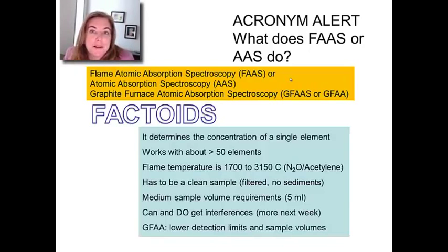Now some factoids about atomic absorption. First, it really is a technique that measures a single element. It's not an atomic spectroscopy that simultaneously looks at everything on the periodic table. The flames are a really important choice in the design. You want those flames to be cheap and easy, so air acetylene is a really good option, getting up to about 2,000 to 2,500 Celsius.